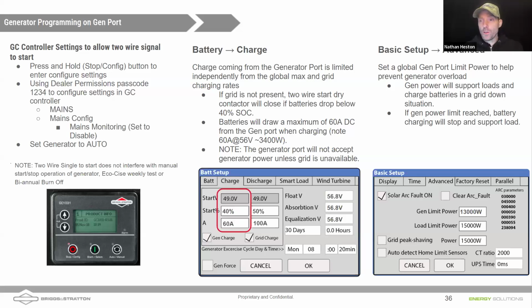We talked a little bit earlier about what these values in the gen charge column mean. So if you have a generator connected to the gen port, that 60 amps is 60 amps DC charging that will occur on your 48-volt battery bank coming from that gen port. Now, keep in mind, if a generator is there, your generator also has to cover loads in a grid down situation while it's charging the battery.